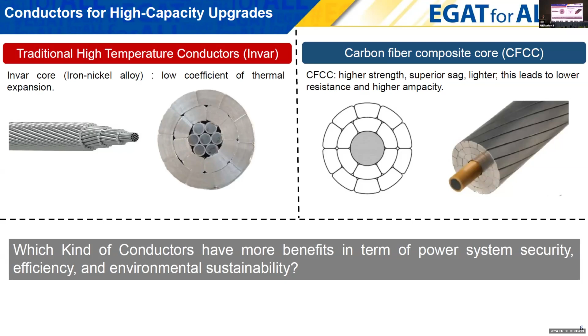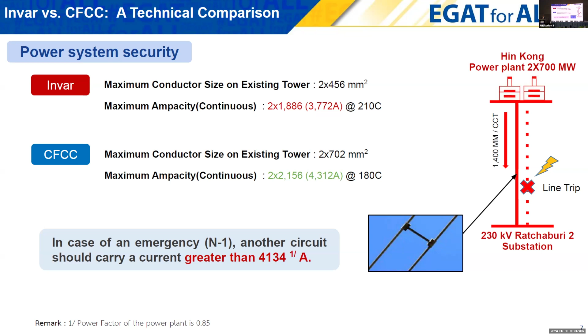This slide shows the technical comparison between Invar and CFCC in terms of power system security. For the Invar conductor, the maximum conductor size on the existing tower is a 2 bundle of 456 square millimeter, and the maximum continuous ampacity is nearly 3,800 ampere. Because CFCC is lighter than Invar, it can use a bigger size, with a maximum continuous ampacity of about 4,300 ampere. In case of an emergency, when one line trips, as you see on the screen, the other circuit shall carry a current greater than 4,100 ampere to accommodate the power from the power plant to the grid.